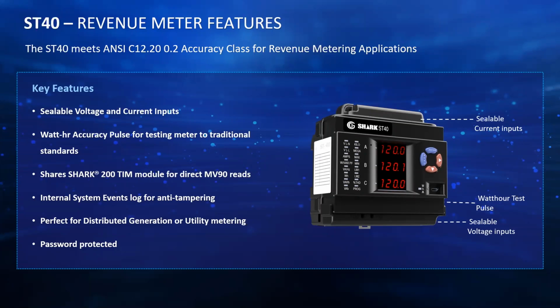We also have a test pulse on the front of the meter for accuracy verifications. When you have the meter in service, you can inject your voltage and current to verify that the meter is still within its 0.2% accuracy anytime down the road that you want to test it. For those of you that use the Itron MV90 billing system, the Shark ST40 uses the same TIM module. If you're familiar with our Shark 200 series panel meter, it uses the same TIM module as that. So this meter is MV90 compatible.